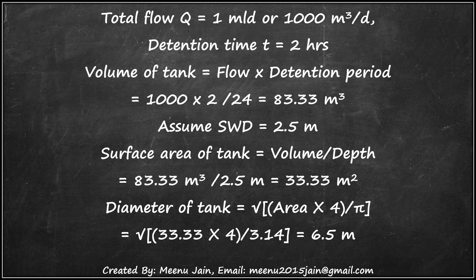From this surface area we can get the diameter of the tank as the square root of area multiplied by 4 divided by pi. That is the square root of 33.33 multiplied by 4 divided by 3.14, which gives 6.5 meters. So 6.5 meters is the diameter of the tank.